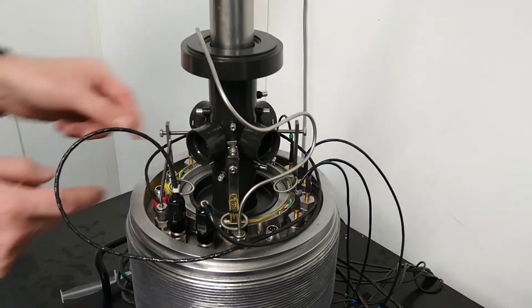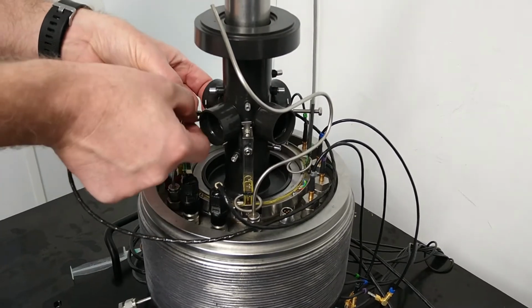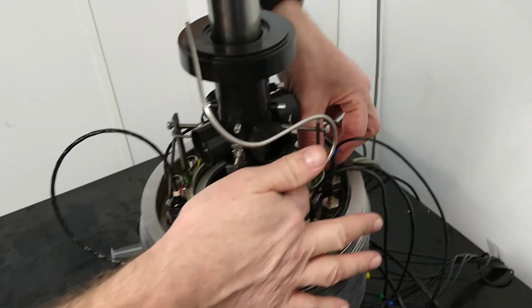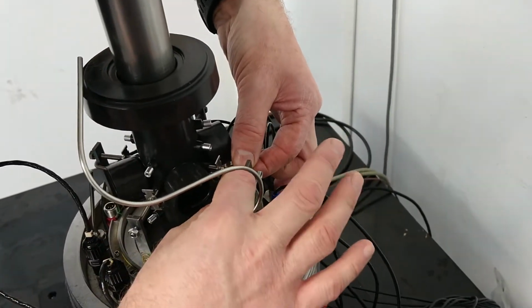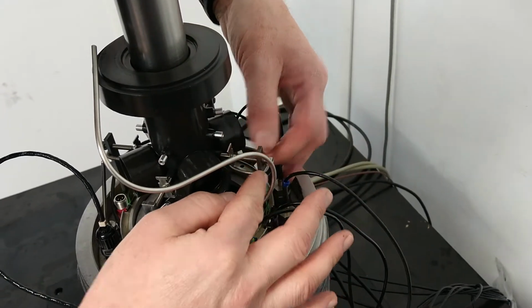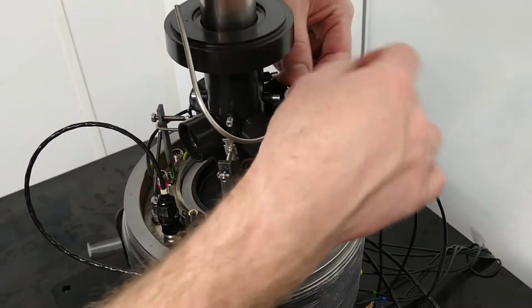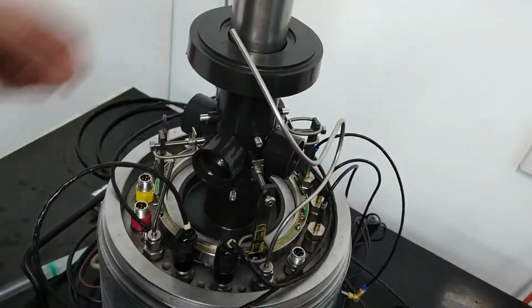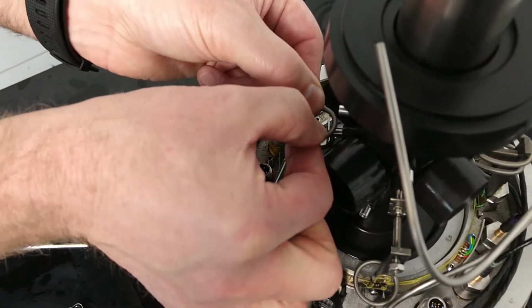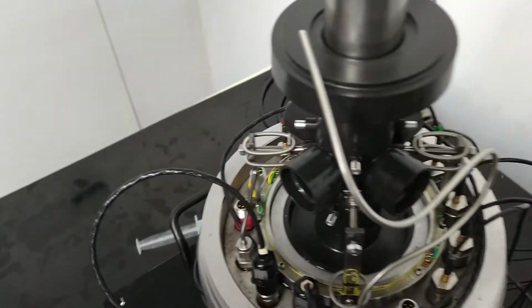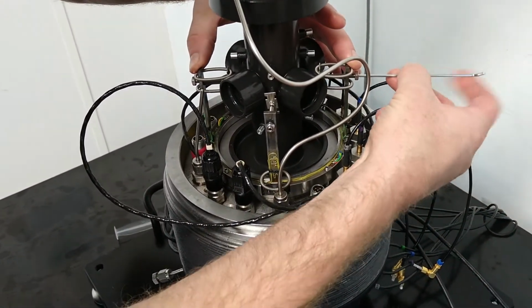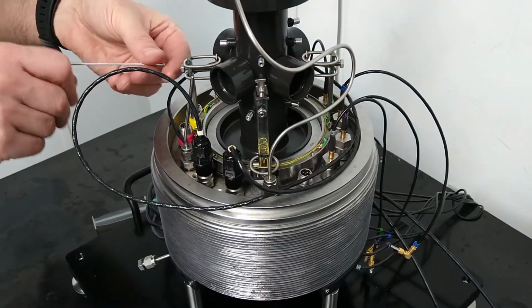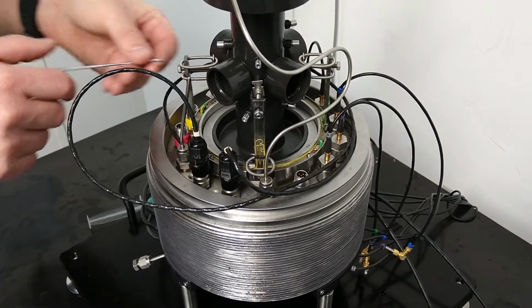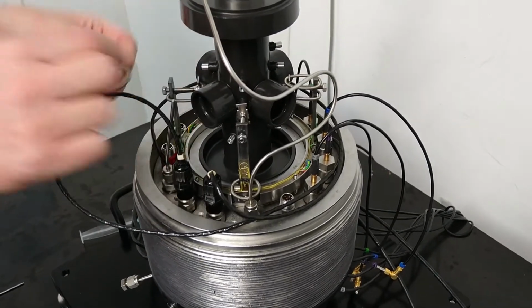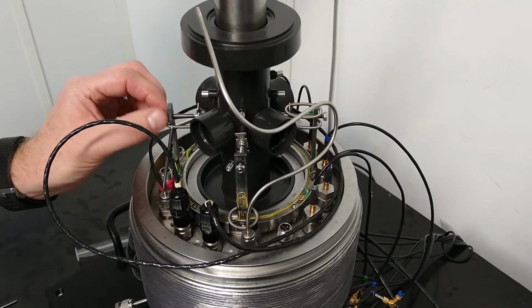This ensures that the measurement range is not exceeded when the caliper is sat in its zero position centrally around the membrane. Attach both the upper and lower springs on each arm, making any final adjustments where necessary to maintain a central position. Once correct, remove the upper spring and fix the locking nut in place. This process should be done in pairs.